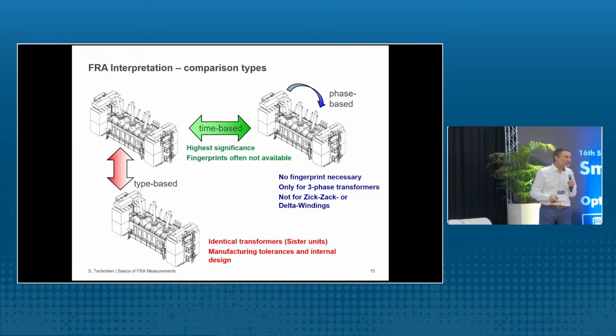But unfortunately, often this fingerprint does not exist, simply because after the factory acceptance test there was no FRA measurement done. So what can you do in this case? You can use a phase-based comparison, so you can compare the phases A, B, and C to each other. Of course, you have to take into account that the middle phase is a little bit different from the outer phase. So you have differences between inner and outer phases, but you know how these differences influence the frequency response. Or you can also do a type-based comparison. So maybe you have a sister unit which has the same design. You can measure there and compare these results.